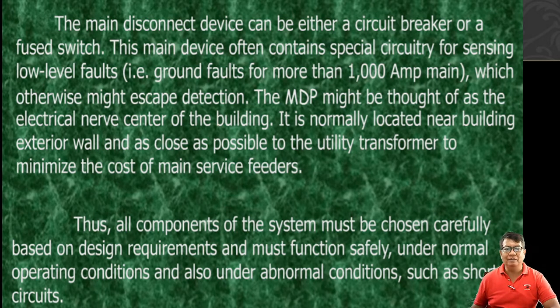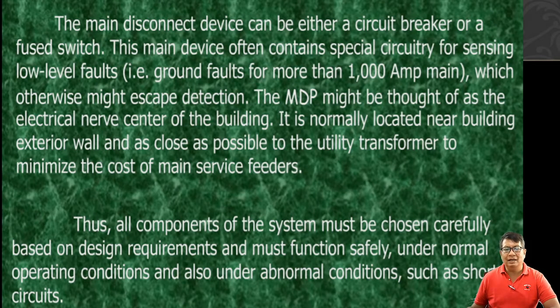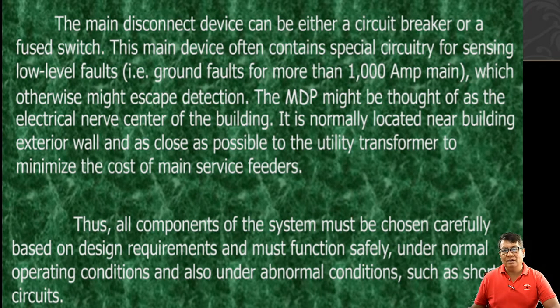The main disconnect device can be either a circuit breaker or a fuse. This main device often contains special circuitry for sensing low-level ground faults for more than 1,000 ampere mains, which might otherwise escape detection. The MDP might be thought of as the electrical nerve center of the building. It is normally located near the building exterior wall and as close as possible to the utility transformer to minimize the cost of main service feeders.